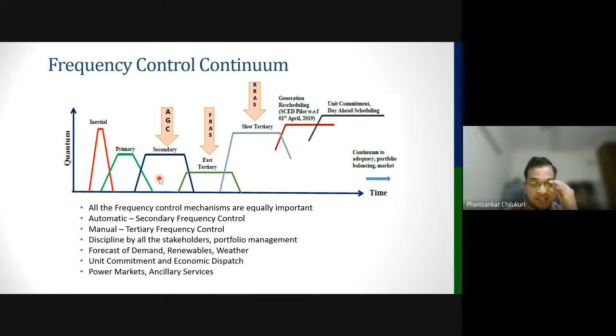This is local, right? Then secondary frequency control kicks in. This is automatic generation control, and every 4 seconds signals are sent from the control room to all the generators to increase or decrease generation. Because we are talking about a generation loss event, obviously we have to increase generation.